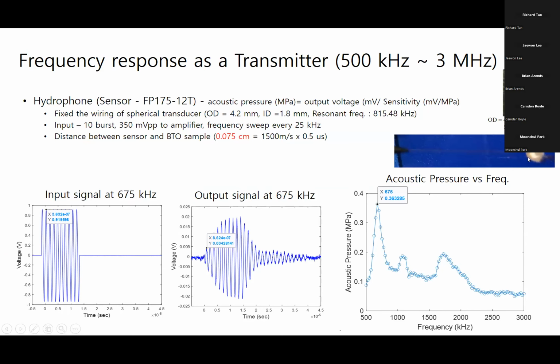When transmitting the acoustic wave to the hydrophone, I did a frequency sweep from 500 kilohertz to 3 megahertz. At 675 kilohertz, the acoustic pressure was the highest value, meaning the resonance frequency of this transducer is 675 kilohertz.